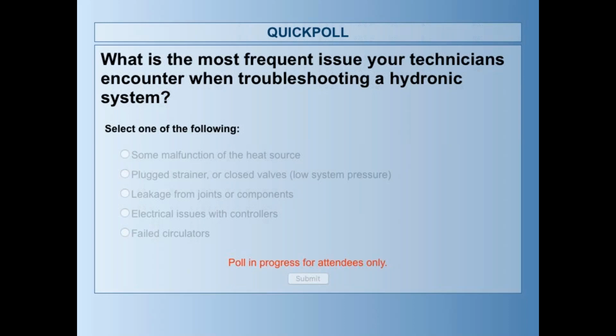Even putting a second pump in will not double that flow rate. And again, you can find all that information if you plot those pump curves and system curves. When you have two pumps in series, you basically double the head at the flow rate. And depending on what the system curve looks like, you will get an increase in flow, but definitely you will not double it. Great, thanks.